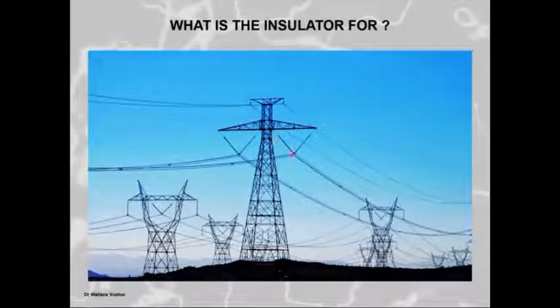Then at the same time, it must be able to withstand a lightning induced overvoltage, a switching overvoltage, and a lightning strike on the tower, raising the tower potential and causing a backflashover overvoltage, okay? So this poor insulator has to be able to handle a lot of electrical stresses. Then at the same time, this insulator is mechanically stressed, because with these long catenaries, these long spans, the wind pushes against the span, and that wind loading also puts mechanical loading. The weight puts loading onto this insulator. So there's a lot of mechanical stresses.